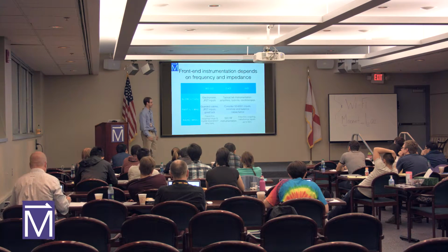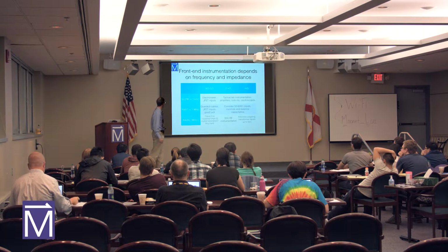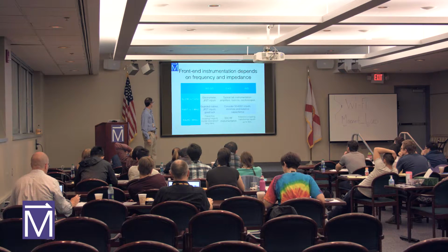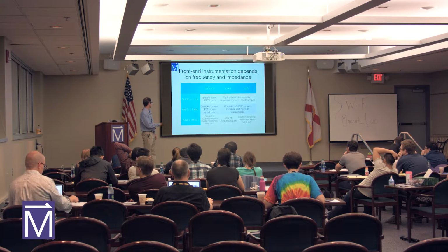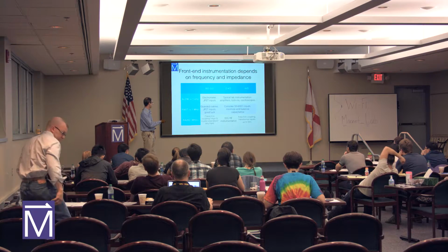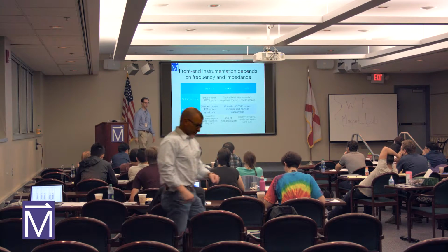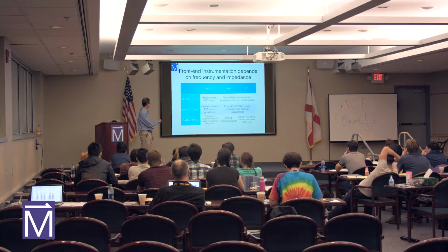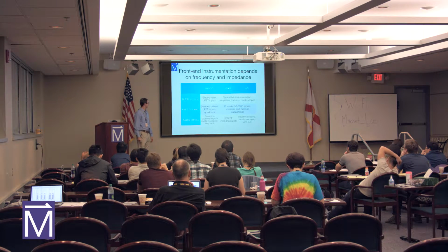How do we deal with different speed and different impedance signals? All right, this is where I wish I had a laser pointer, and I do. OK. So the world we live in here at the lab tends to be in here. And if you're doing two-dimensional science, some of these graphene projects, you may well be living here. So in the high megaohm range and going fairly slowly. So if you are trying to go faster, this is when you have to start getting creative.